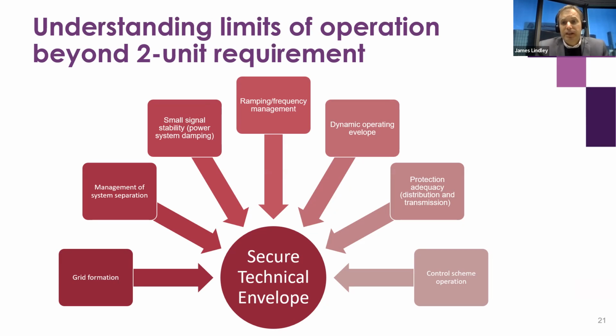A tricky one we've been working closely on with the network companies, both distribution and transmission, is making sure there's adequate fault current for protection operation. This requires a fair bit of work by those companies to calculate what adequate fault current is needed at critical parts of the network and to make sure the setup can maintain them.